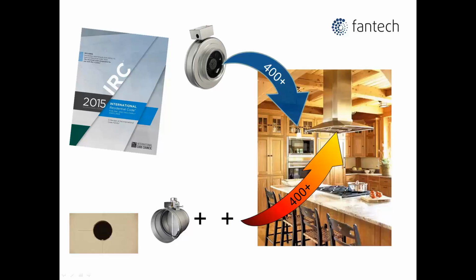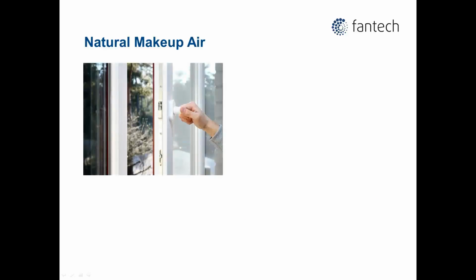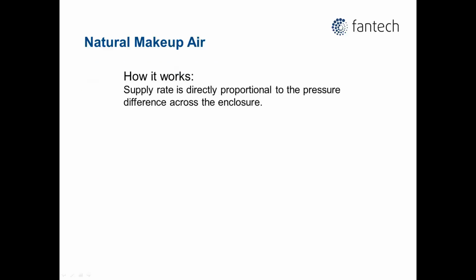Well, go figure. Sucking air through a hole needs a pressure differential, in this case depressurization, just what the code was designed to stop. So let's look at this damper or natural makeup air option. Natural really means a hole in the wall, just like an open window or door. This is a fancy way of saying that air is sucked in by depressurization from the exhaust fan. Oops! Depressurization, just what the code was written to prevent.